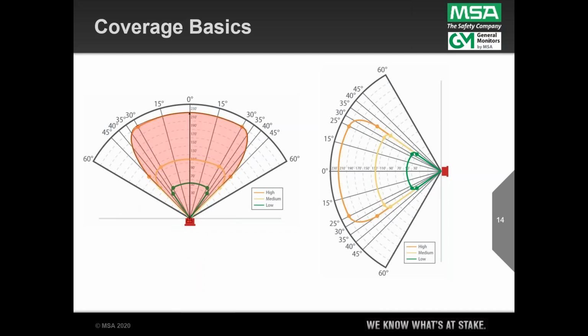So the first thing we do is replicate these audited and validated coverage maps and bring them into AutoCAD or a drawing program, and then examine the coverage provided by different detector locations and different mounting angles. A precursor to that is prioritizing the highest risk ignition zones in the facility that we need to cover. So with this coverage template and a fire zone definition, highest to lowest priority, we can then answer that question.